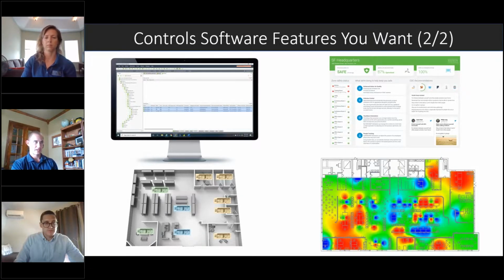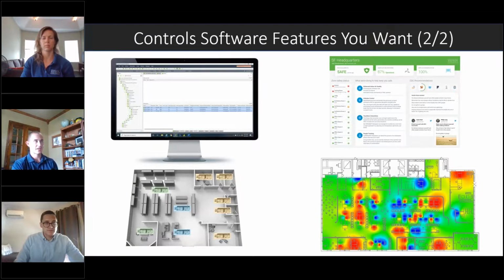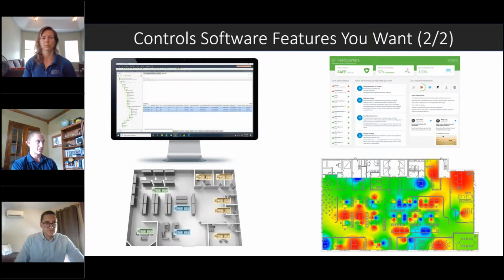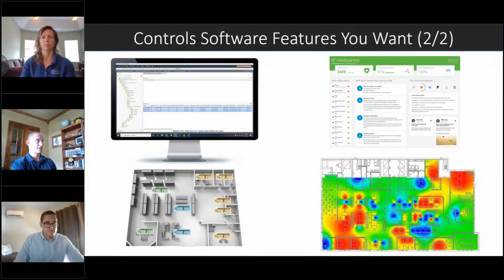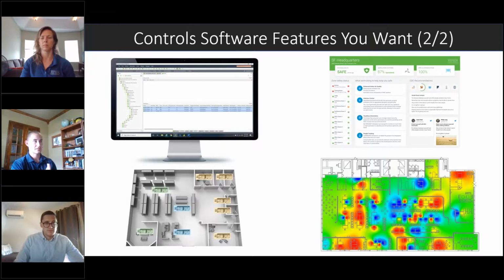And what it'll do on the VAVs is check the air valve test. So it'll check for reverse damper. It can actually auto-correct a reverse damper if it sees it. It looks for airflow leakage on the minimum and on the maximum. And then it looks at whether the damper is not moving or is obstructed or stuck.